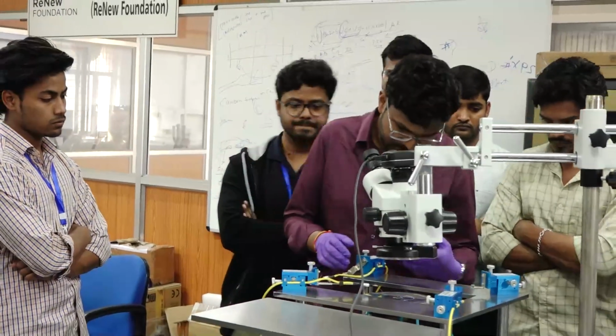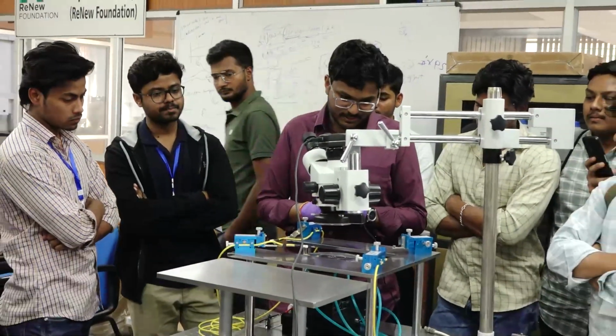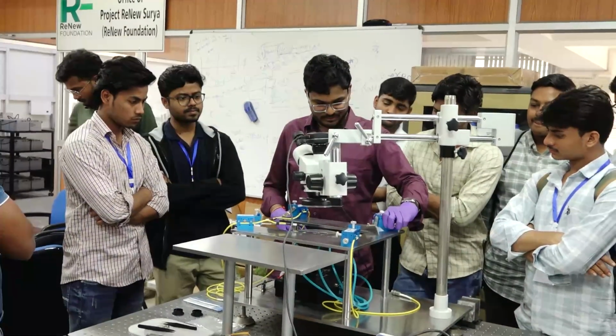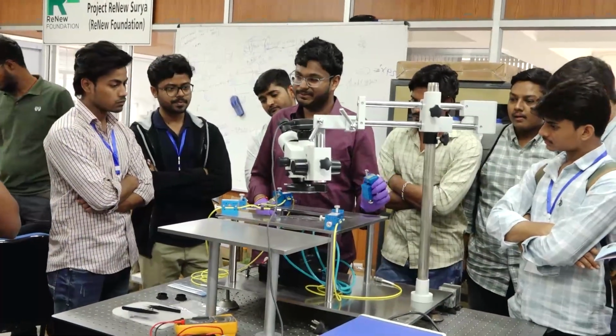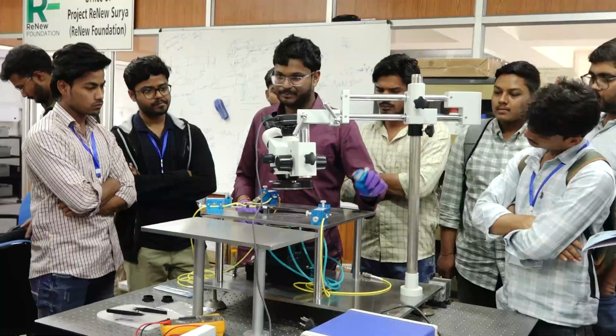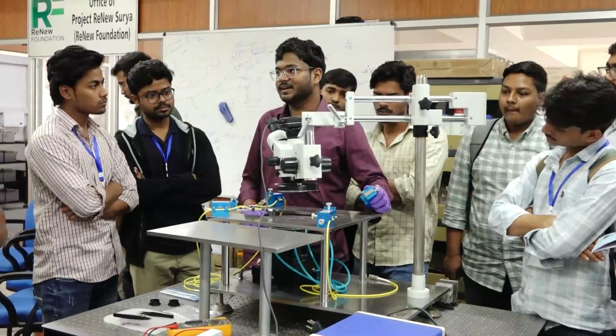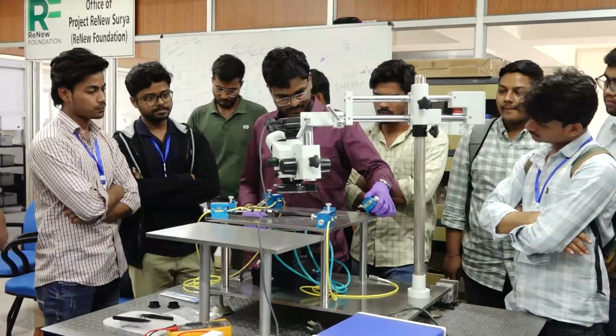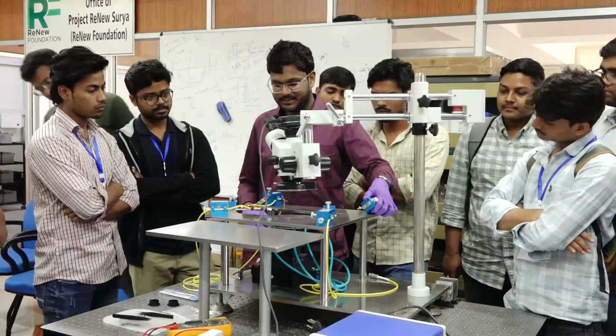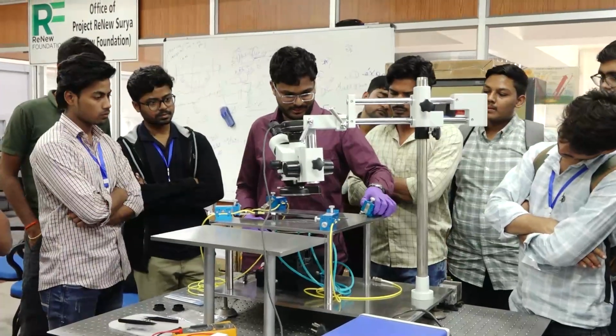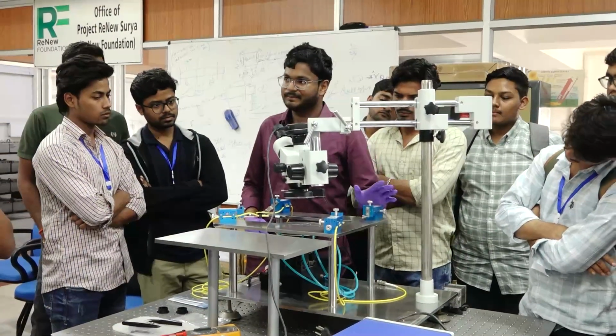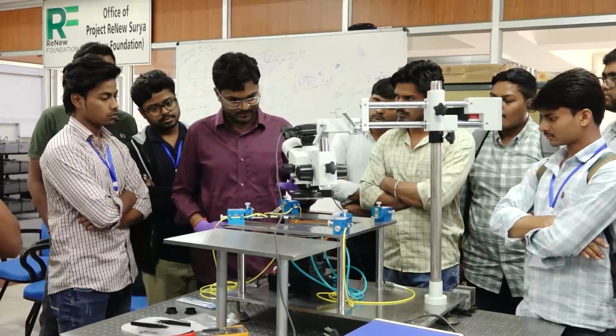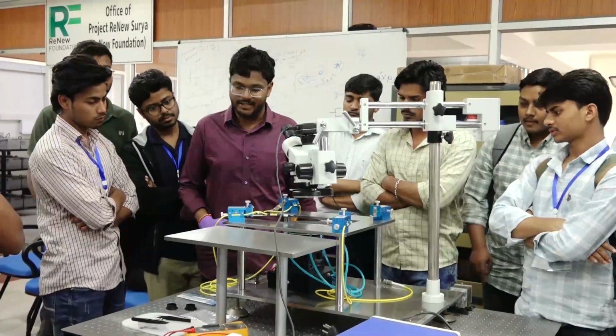These magnetic-based micropositioners are not supposed to be dropped directly. You are not supposed to place them hard on this plate. You have to tilt it, place it in a tilted position, then slowly bring it down. Otherwise it can have some mechanical movement inside and damage the positioner.